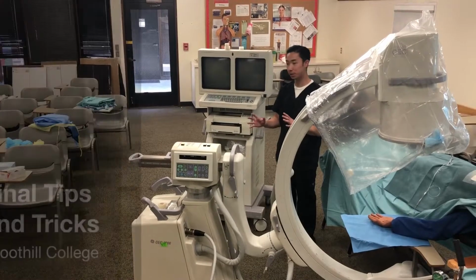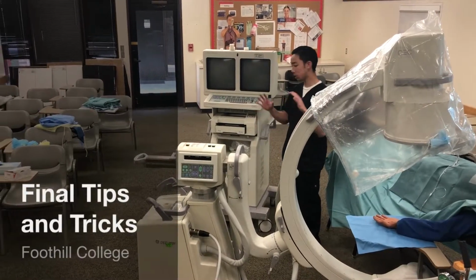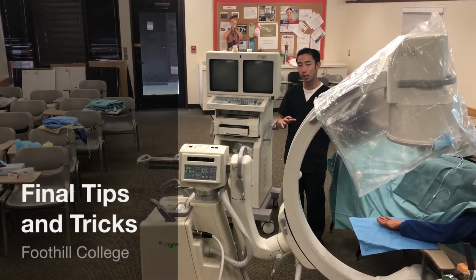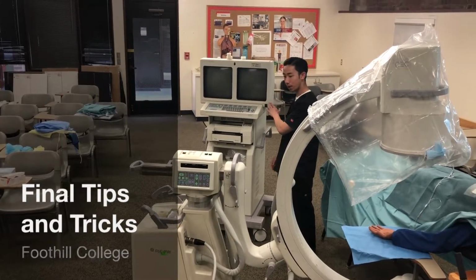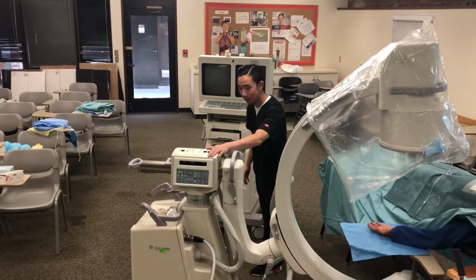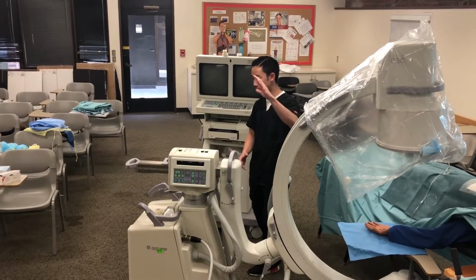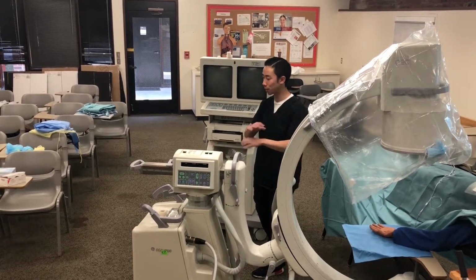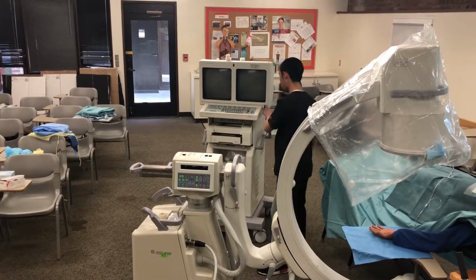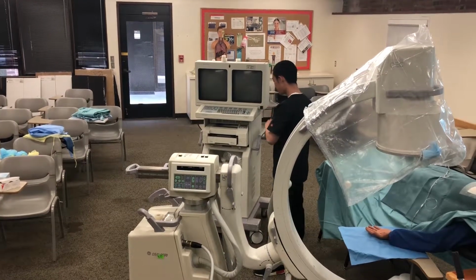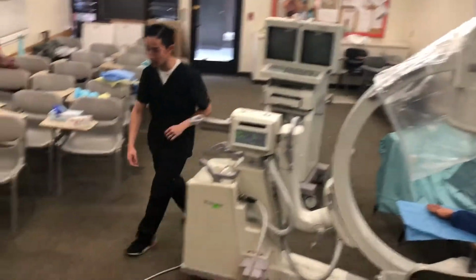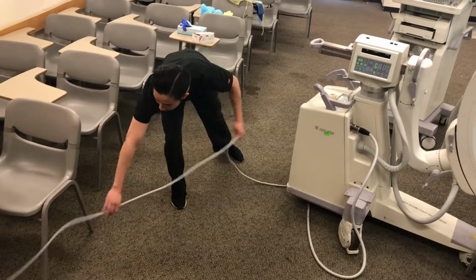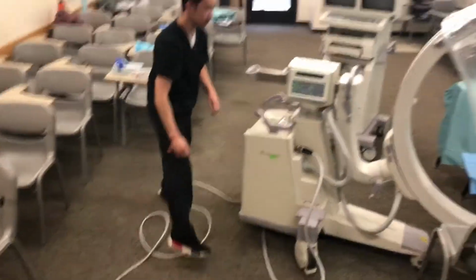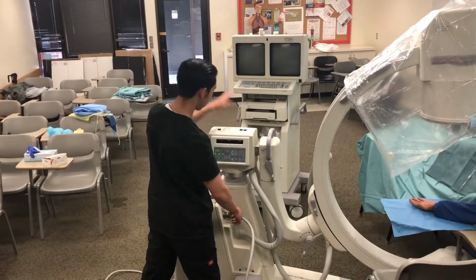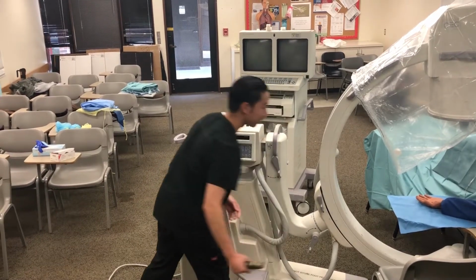All done with the C-arm. If you're ready to turn it off, you turn it off in the reverse order you set it up in. So before you turn off the monitor, you want to make sure that your tower is all the way down, because if you turn it off and it's still partially up, there's no way to get it out without rebooting the entire system. So you would start with this, turn that off there, then you would unplug the power supply from the wall, and lastly, you would unplug the C-arm from the monitor. And then you're good to go.